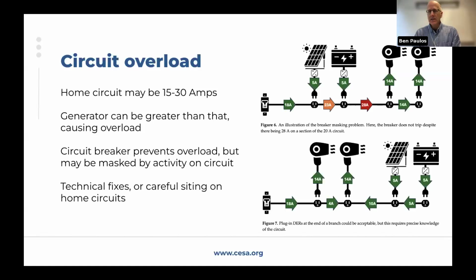To me, this seems like a rare circumstance, but that is UL's job, to assume the worst. So in the bottom case, the two hair dryers are upstream on the circuit, closer to the circuit breaker. And in this case, the solar panel and the battery at that time are putting out 10 amps, and that actually helps power those hair dryers. So the effective load on the circuit is only 18 amps, and the circuit breaker thinks it's fine, which it is fine, because you see it's all green arrows and there is no overload along the line.